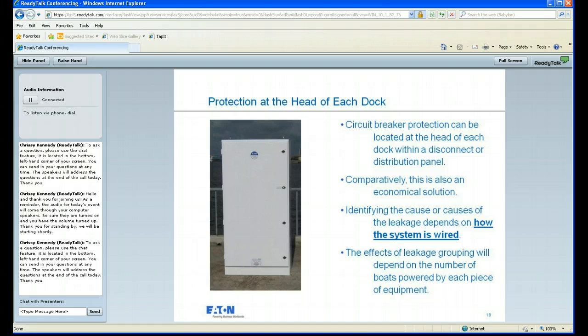I agree 100% with what you're saying. That's the most economical place to put the GFP. However, it depends on the design of your marina. If you're supplying the marina from the utility with 480 volts because of voltage drop concerns, and then you're stepping voltage down on your marina with transformers, putting the GFP at the main will not detect ground faults on the secondary side of the step-down transformers. So you need to be very careful in the way you put that. If you put the GFP at the main, you also will be required to put it on the secondary side of each of the step-down transformers to detect the ground faults on those separately derived systems on your marina.